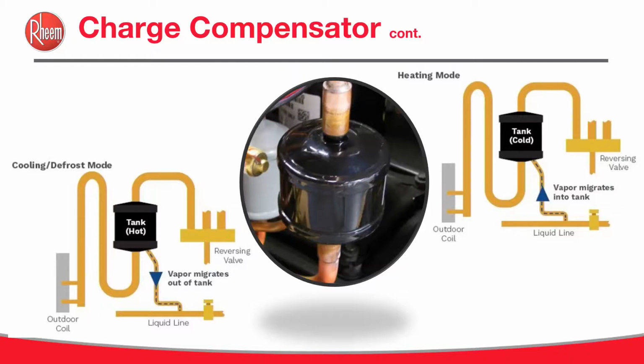So notice the refrigerant is now stored in the compensator in the heating mode. So in cooling mode on this one, the tank is hot, right? Or defrost mode. And in heating mode, the tank is now cold. So as we said, remember, the charge compensator is not required for an air conditioner, as the refrigerant only flows in one direction.